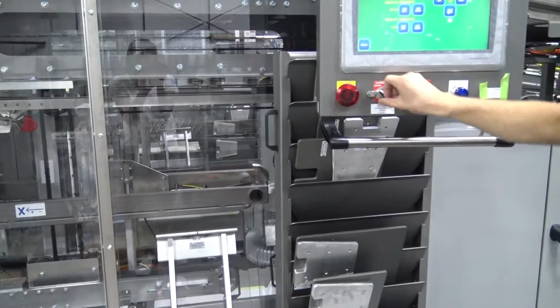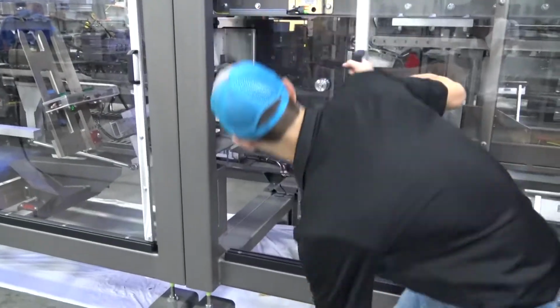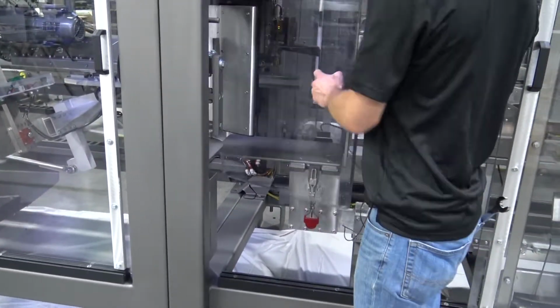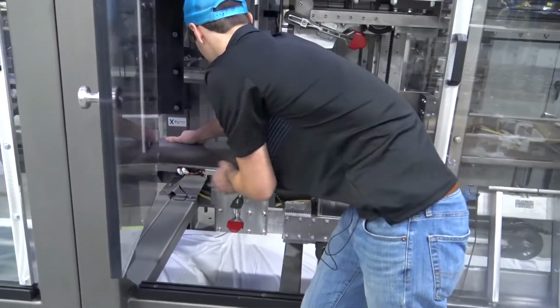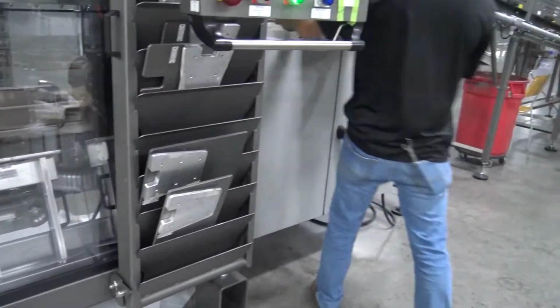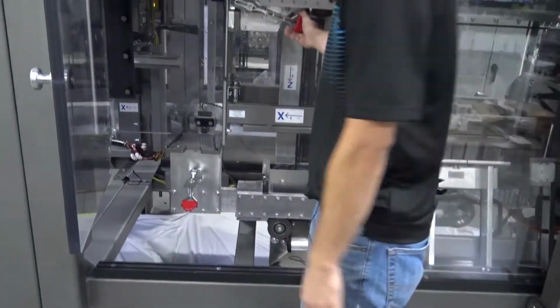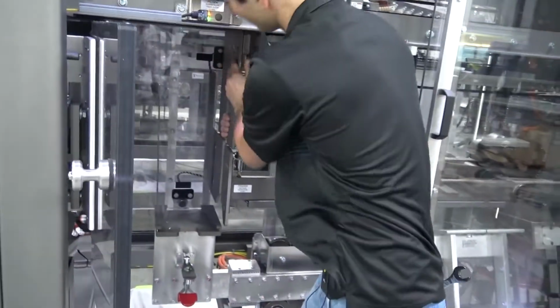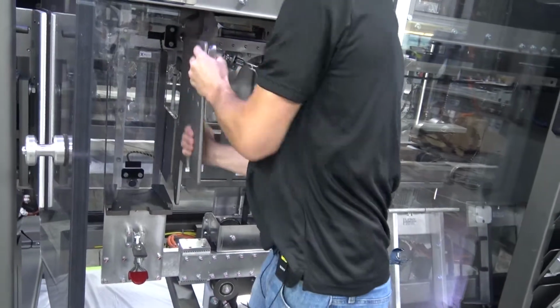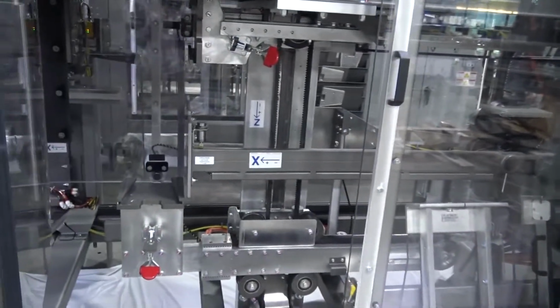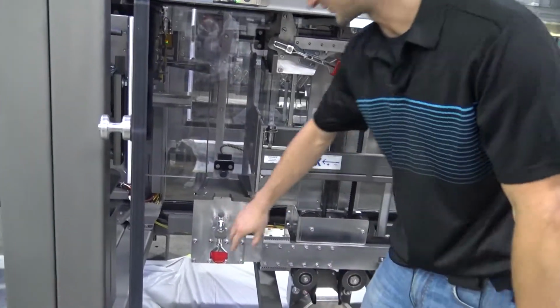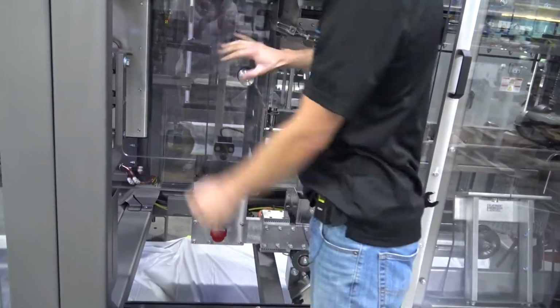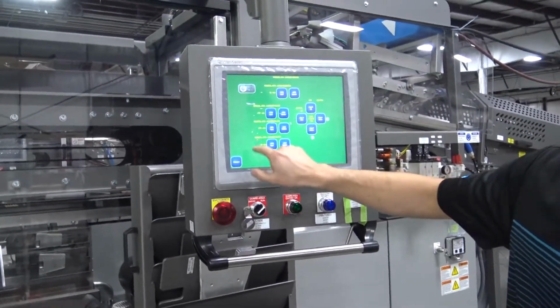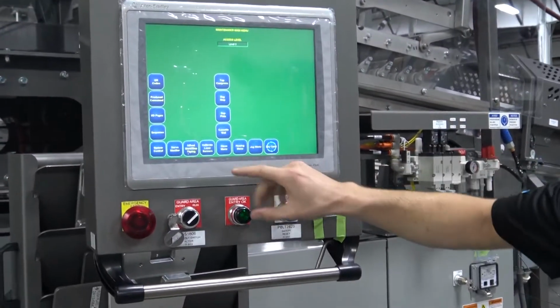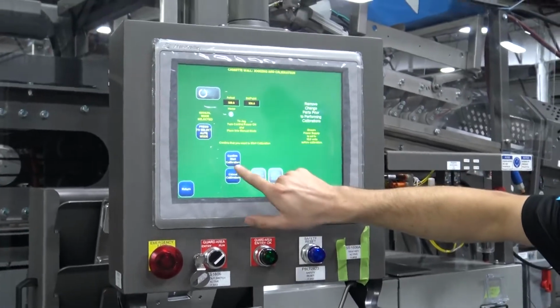So I'm going to enter the machine. Remove the lift plate, put it aside, and then also remove the pusher plate. Close the clamps back up, and close the change part loading, or the change part door, and the door. So now I'm going to go back to my calibrate screen to do the calibration now that the change parts are removed. Again, go into manual mode and confirm I want to start the calibration.